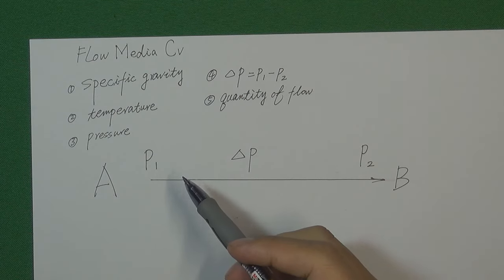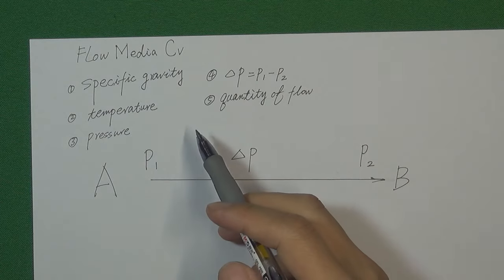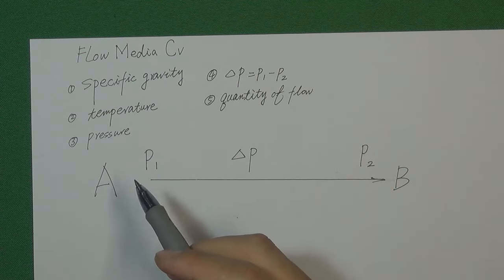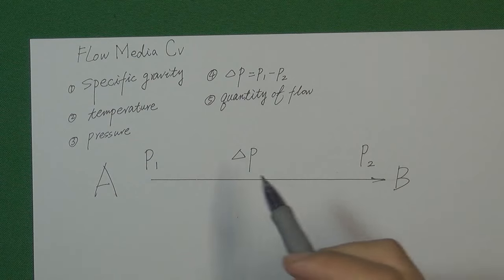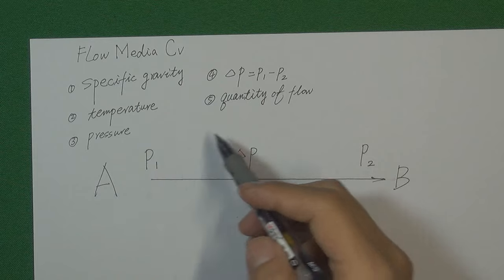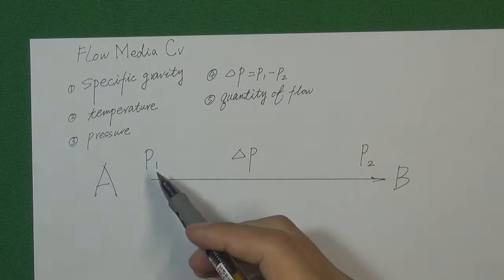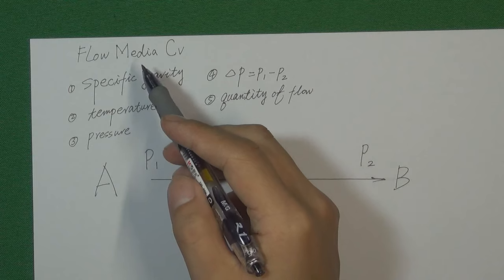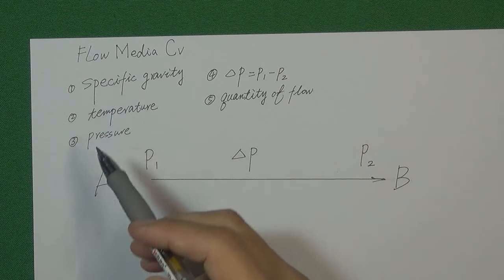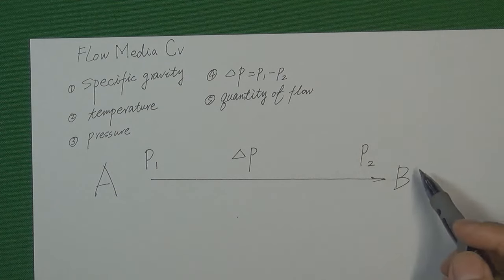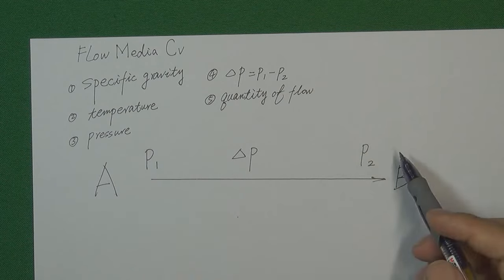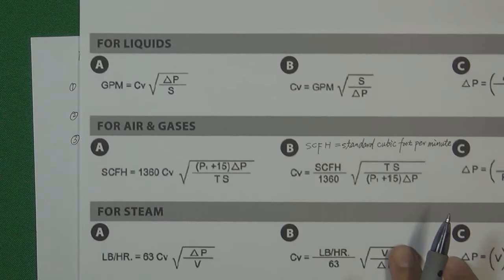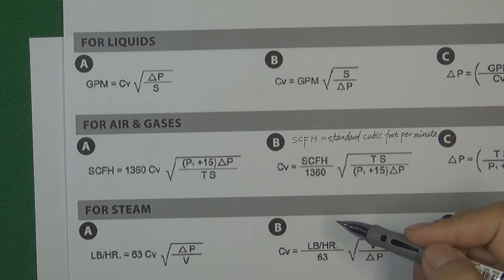To understand the relationship between valve CV and flow medium CV, first we need to understand what is flow medium CV. Flow medium CV tells the engineer how much flow medium we are going to transfer through the valve from one side to another. We get the flow medium CV by calculation from five design factors about the flow medium and the flow control system: the specific gravity of the medium, the temperature of the medium, the pressure pushing the medium, the differential pressure from one side to another, and the quantity of flow.